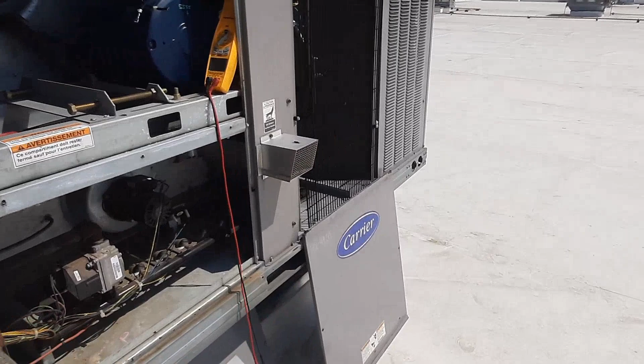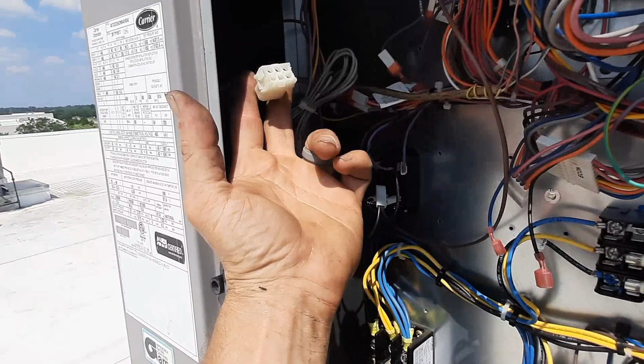Plug that terminal block on. I need to get a call, which I'm assuming I don't have yet because my contactor's not pulled in. Everything else is disconnected. Yeah, while one's off, we'll give it its time delay. It shouldn't be able to pull anything in there. My fan motors will run. We'll plug them on one at a time. Make sure the fan motors run, then I can button all that up, and then I'll come back to figure out what's wrong on this side. This is gonna be my problem, somewhere between the relay and those motors.